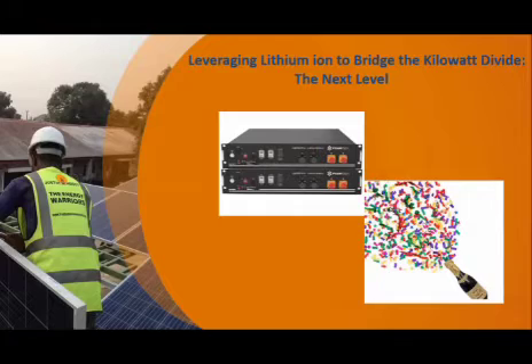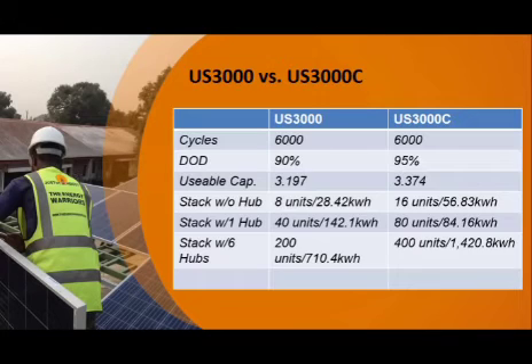So just like Francisco and Owe have said, we are introducing a new set of batteries from PYLONTECH, and that battery is the C version. We're going to start off with the 3000C, and as you can see from the next chart, the differences between the C and the 3000 regular is that the depth of discharge moves from 90% to 95%.